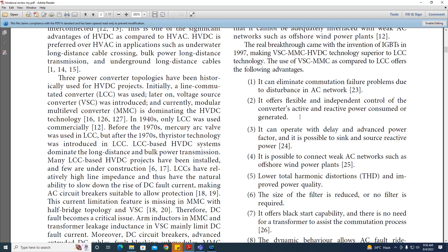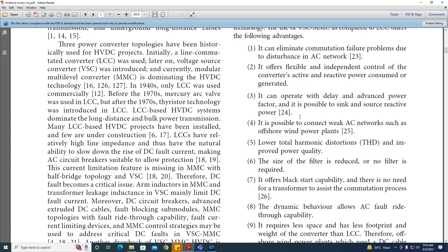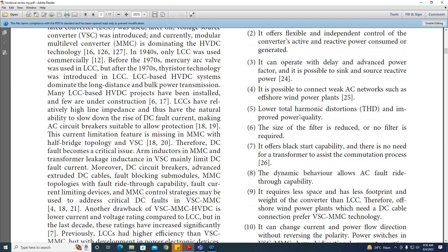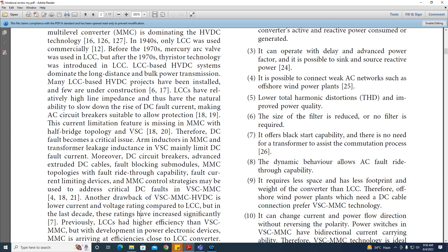Here we mostly use synchronous reference frame theory or vector current control principle, and in that principle it is very possible that you can control the active power by controlling the D component of current, which is real quantity, and reactive power can be controlled by controlling the Q component of the current, which is imaginary quantity. So independent active and reactive power is possible. It can operate with lagging and leading power factor, and it is possible to sink and source reactive power in case of VSC MMC. It is possible to connect weak AC networks such as offshore wind power plants, THD, improved THD, lower THD is possible, improved power quality is possible.